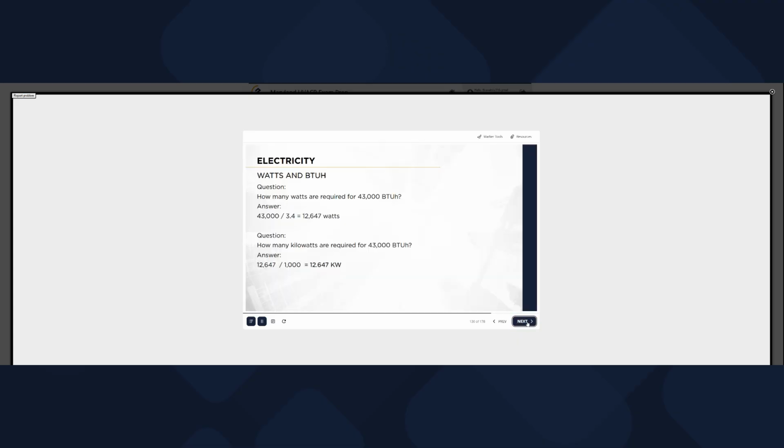How many watts are required for 43,000 BTUH? 43,000 divided by 3.4 equals 12,647 watts. How many kilowatts are required for 43,000 BTUH? Answer: 12,647 divided by 1,000 equals 12.647 kilowatts.